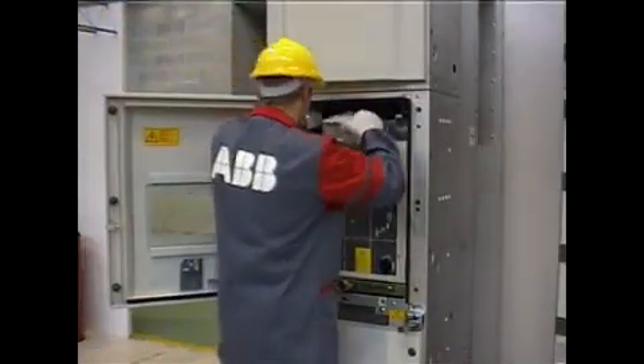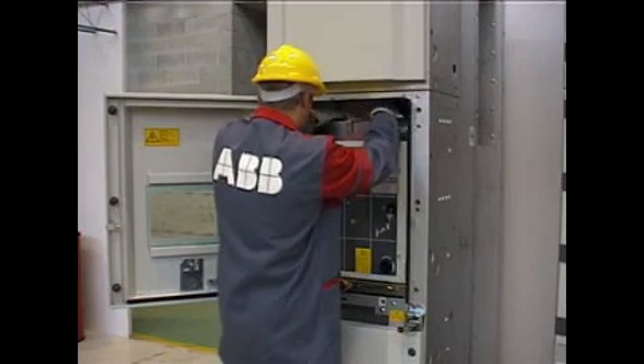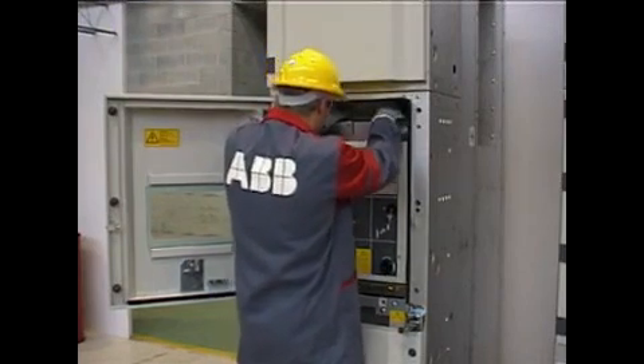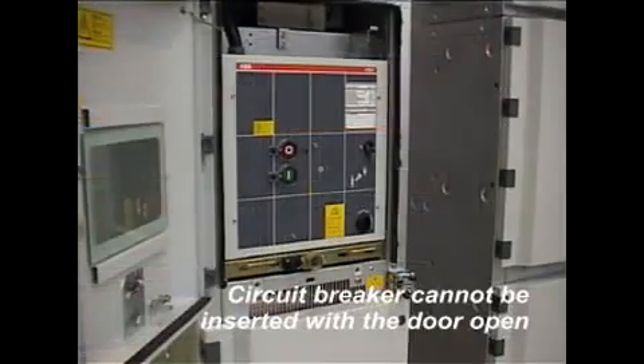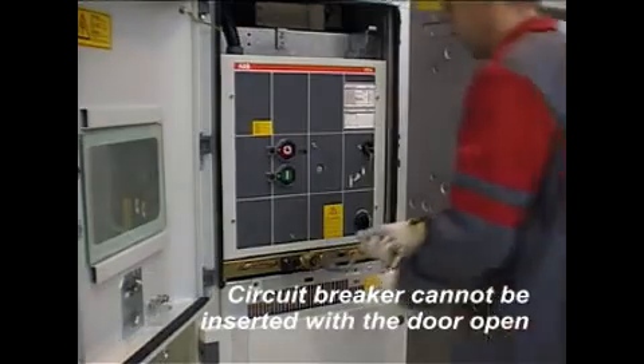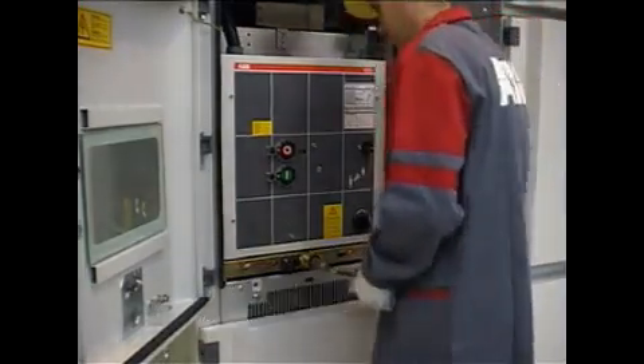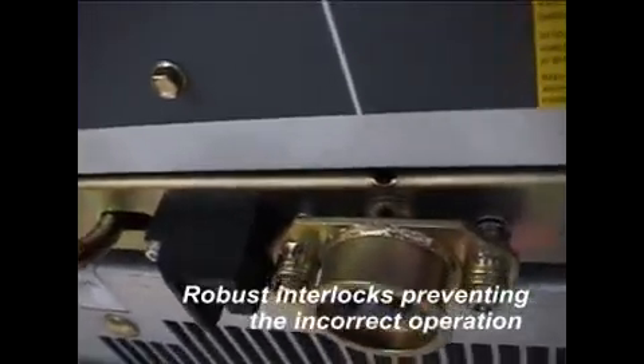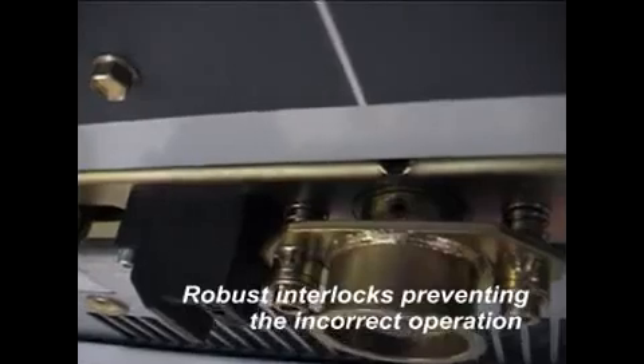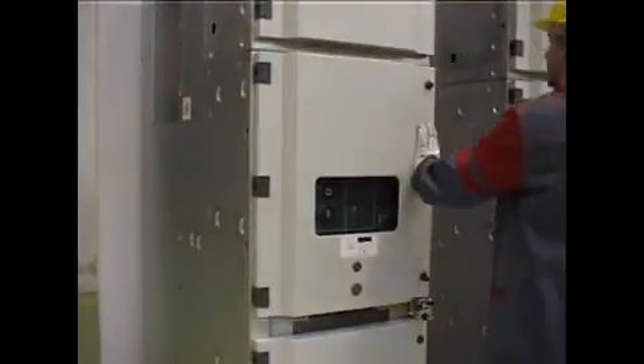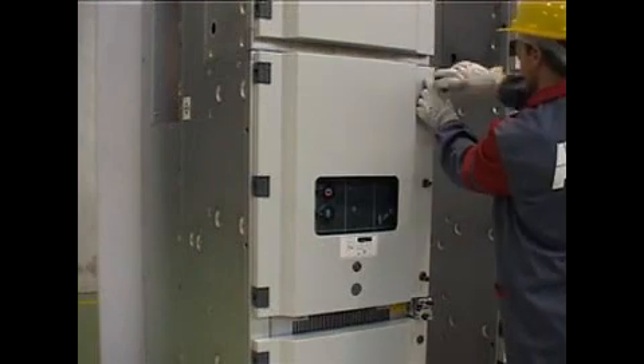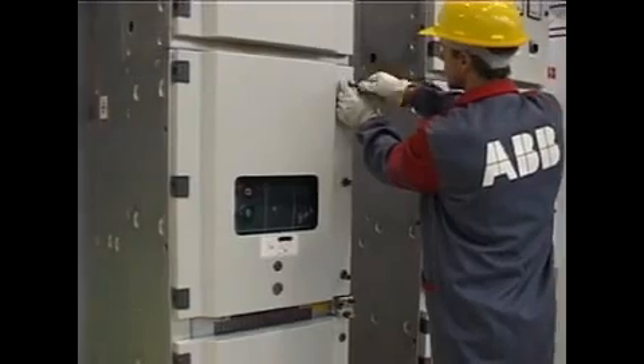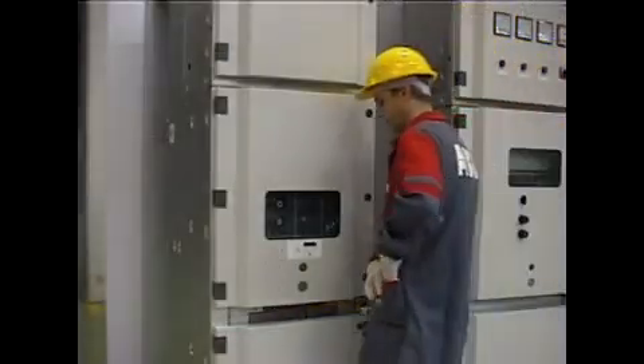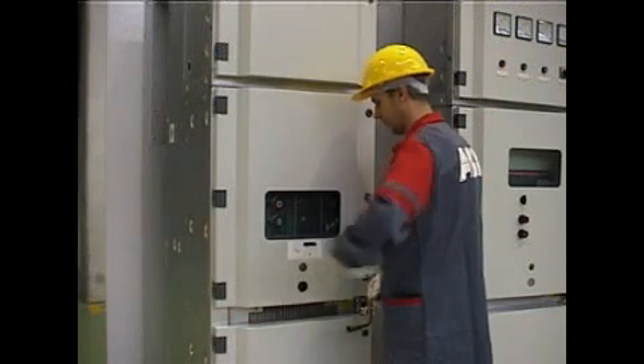We can now insert the breaker and then reconnect the auxiliary plug to have the breaker ready in test position. At this point, the circuit breaker cannot be inserted with the door open, because this could lead to a dangerous situation in case of a fault. This lock is achieved on the circuit breaker shaft, thanks to a stud located on the door. With the door closed, we can safely insert the circuit breaker in the cubicle.